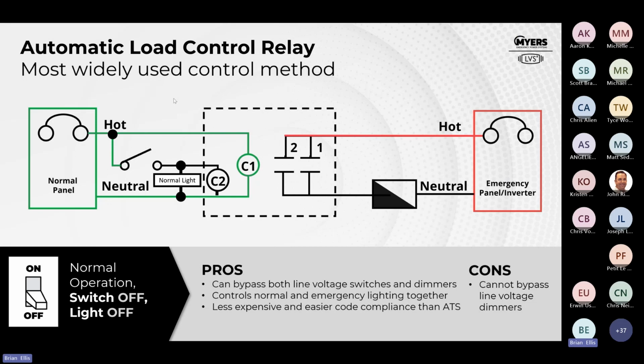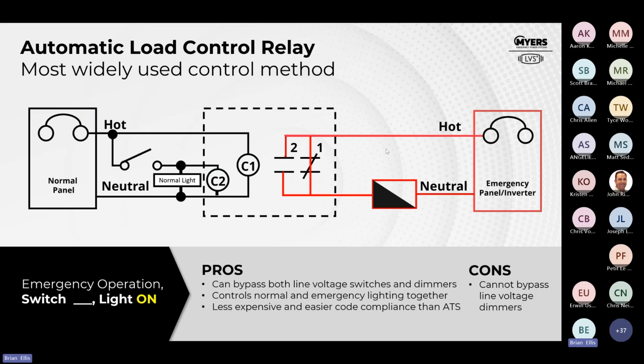That's one thing to note, right? UL 924, the device never powers the emergency light from normal. Really, all we're doing is opening and closing two separate contacts. So this works all day long, allowing my normal and emergency lights to come on and off together until utility fails, in which case the shunt relay kicks in and provides an alternate path to that emergency fixture.